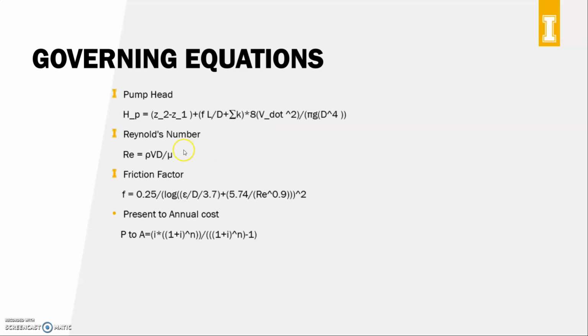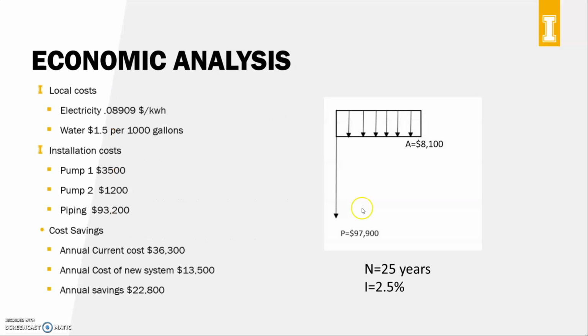Now, we also used, of course, our Reynolds number. Our Reynolds number comes out to rho V, which is velocity, d, which is diameter, over mu, which is our viscosity, and our friction factor. This is the Swamee-Jain equation, which is 0.25 over the log of the relative roughness divided by the diameter divided by 3.7 plus 5.74 over the Reynolds number to the 0.9 power, and that's all squared. And we also use the present to annual cost equation, that's P to A as usually referred to, and this is to convert our present cost to an annual cost over the course of our N. In this case, as I said before, our N is our 25-year span, and our interest is 2.5%.